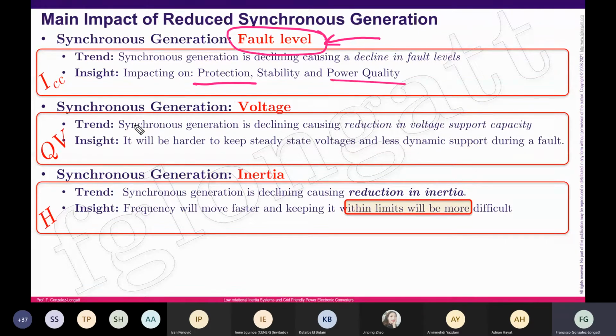Also related is power quality. The second issue with reduction of synchronous generation is voltage control: as we reduce synchronous generation, we reduce the power system's capability to control voltages, because we're reducing the sources of reactive power.